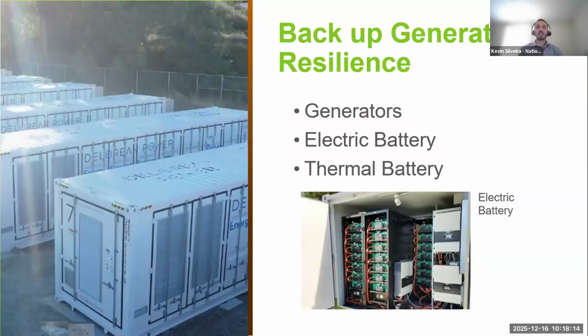Also, when thinking about electrifying your building, you need to keep in mind backup and resilience for your building. If your current building is on a generator that's sized to do the boilers, that system will not be sized to do a heat pump system. You are really increasing your electrical consumption, so you need to take that into account. But we can install electrical battery backups or thermal battery backup as a way to offset the existing generators. There are technologies that are advancing every day that could help assist that.